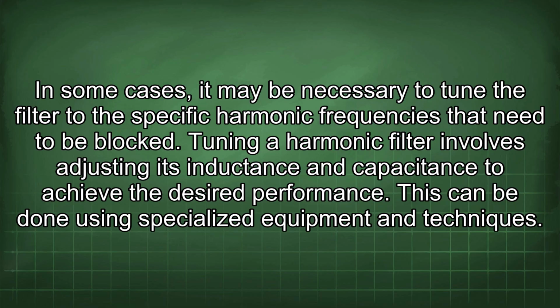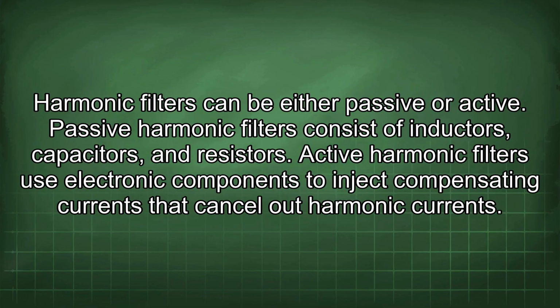In some cases, it may be necessary to tune the filter to the specific harmonic frequencies that need to be blocked. Tuning a harmonic filter involves adjusting its inductance and capacitance to achieve the desired performance. This can be done using specialized equipment and techniques. Harmonic filters can be either passive or active. Passive harmonic filters consist of inductors, capacitors, and resistors. Active harmonic filters use electronic components to inject compensating currents that cancel out harmonic current.